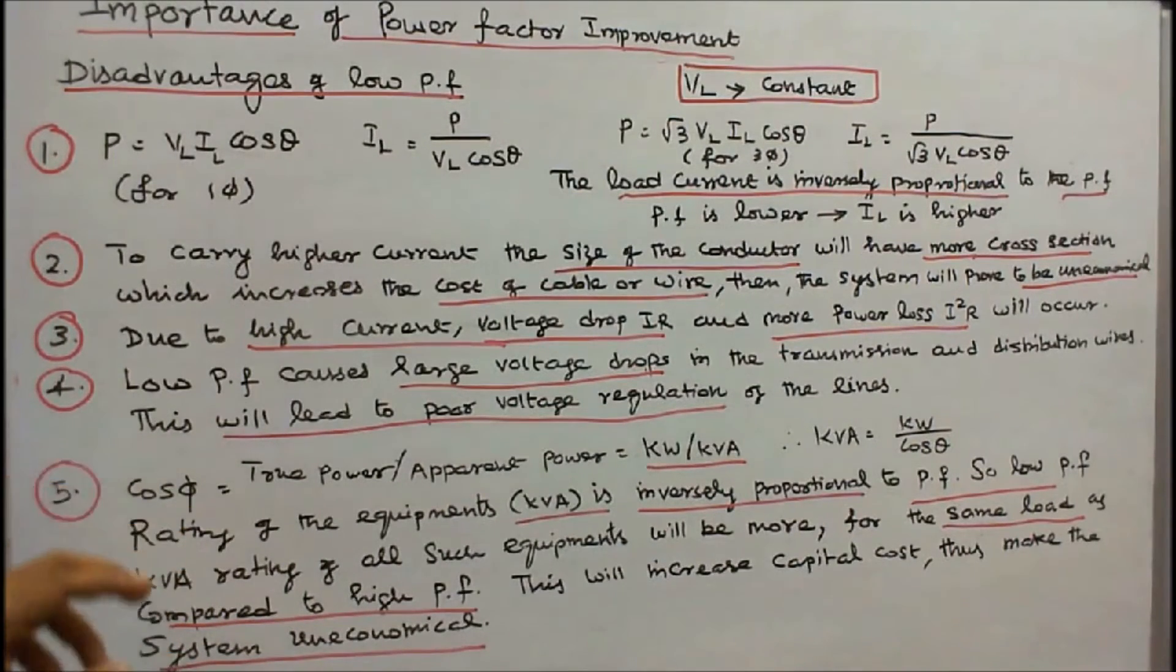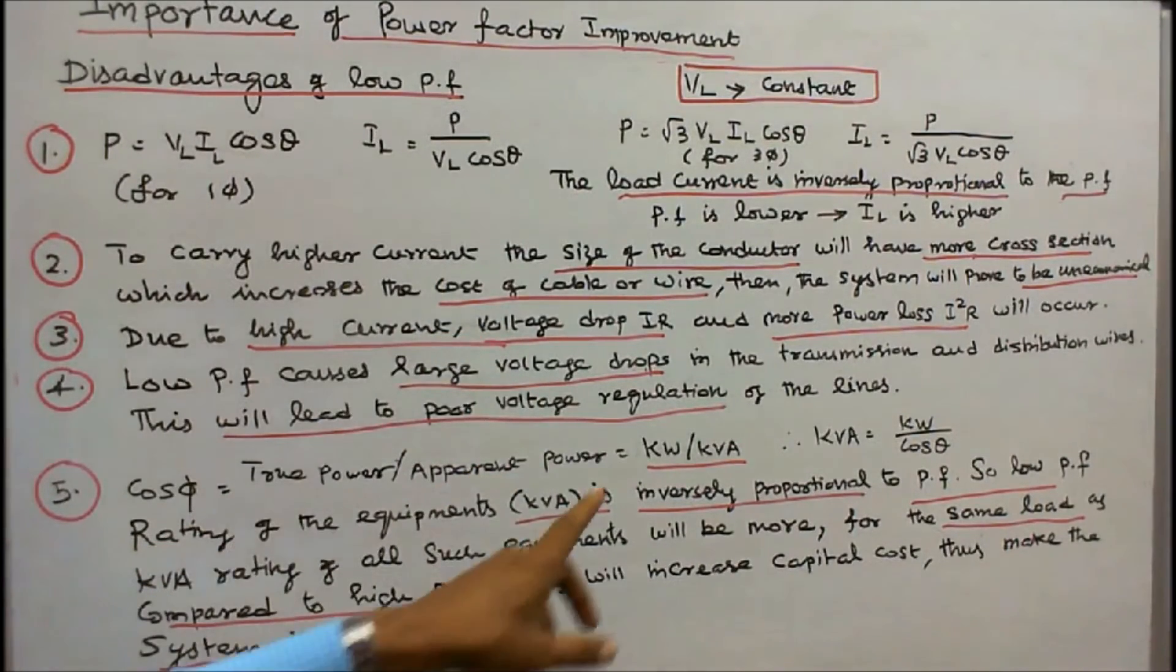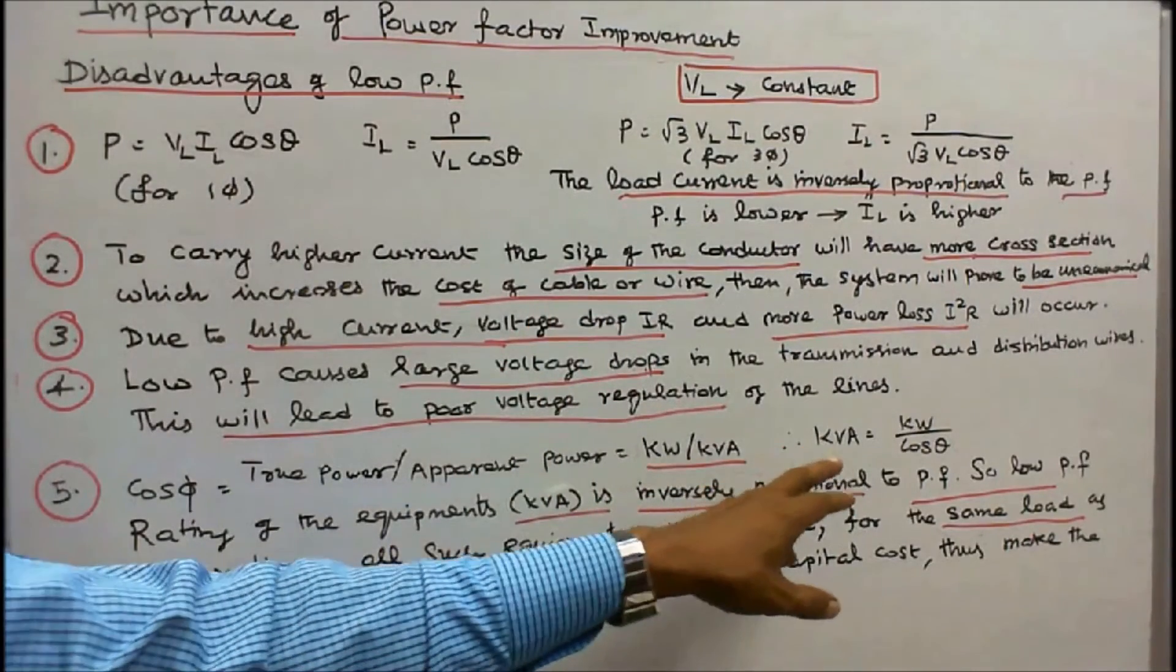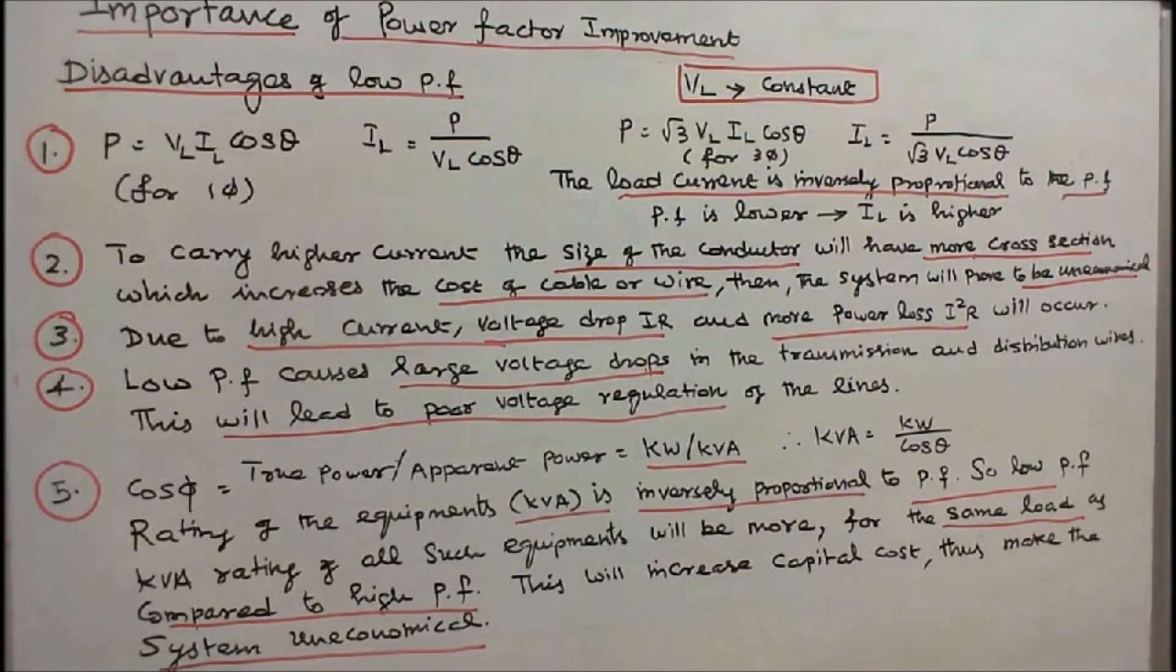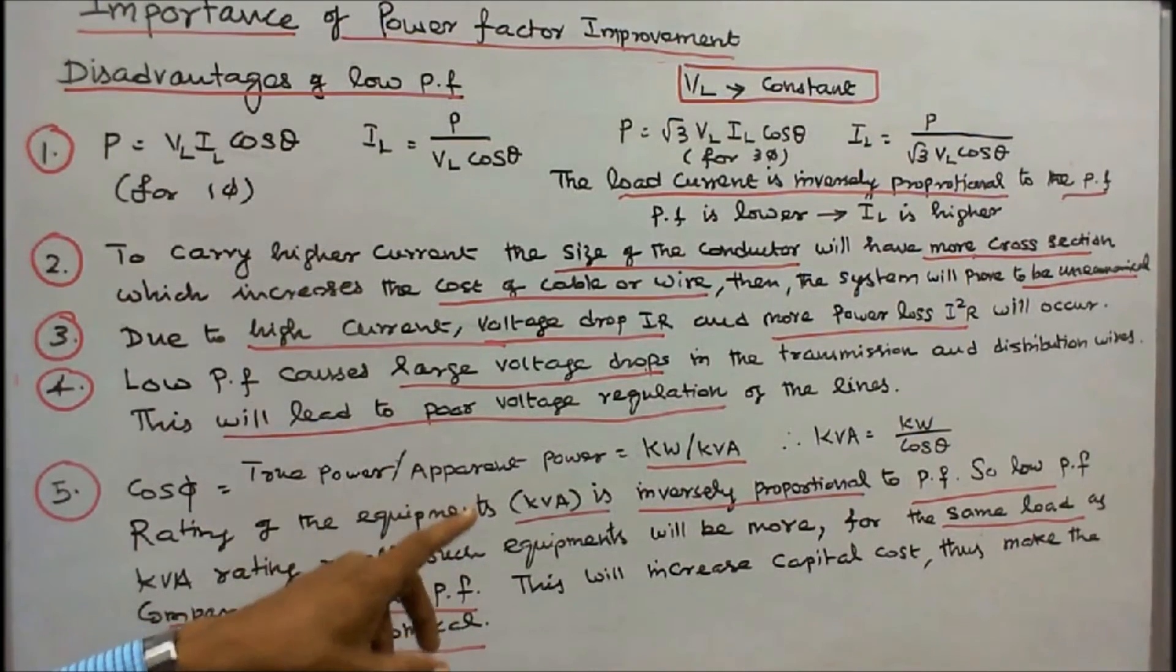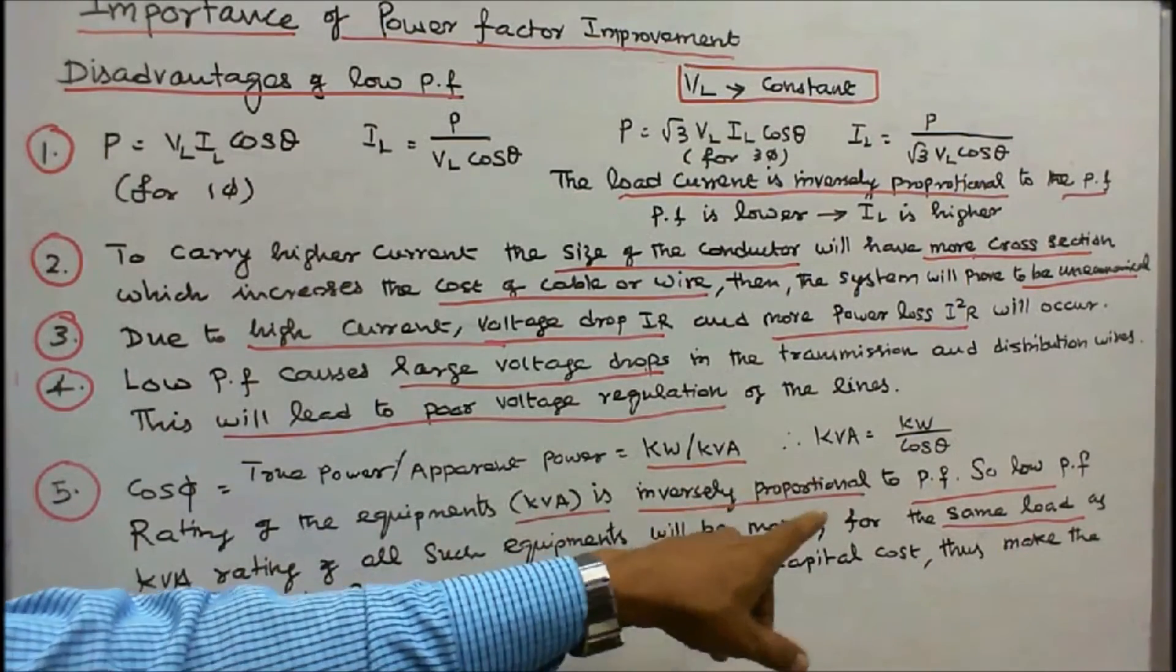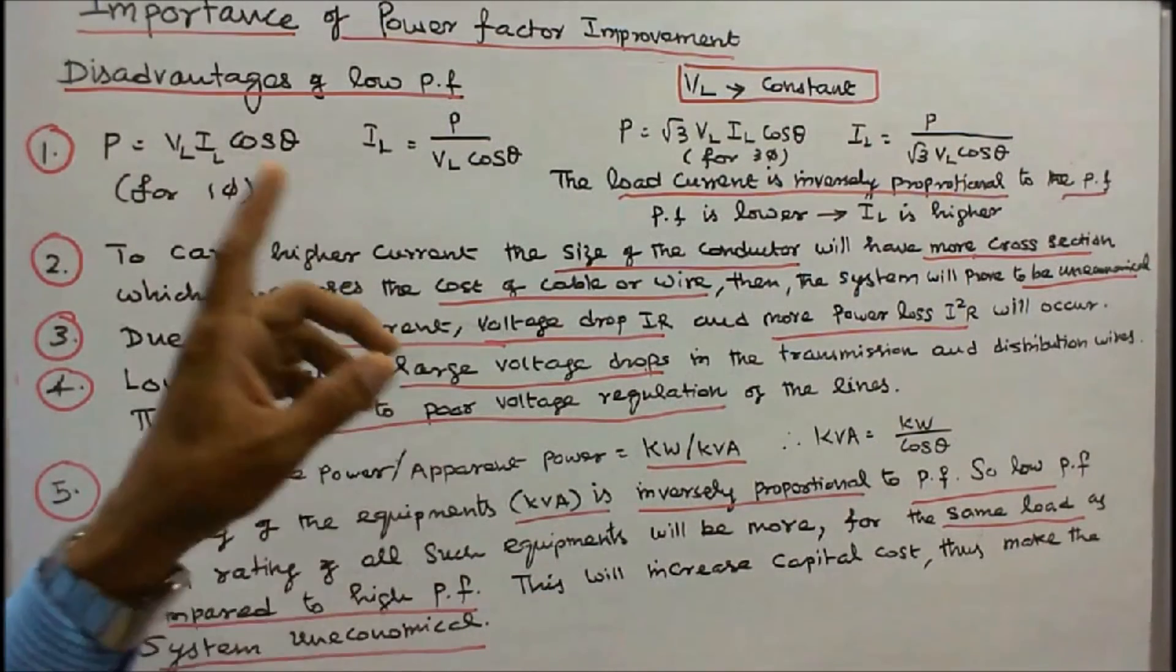Number 5: Cos φ or cos θ is equal to true power divided by apparent power, that is equal to kilowatts by kVA. Therefore, kVA is equal to kilowatts divided by cos θ. Rating of the equipments—transformers, alternators—are rated in kVA and is inversely proportional to power factor. So low power factor means the kVA rating of all such equipments will be more for the same load.